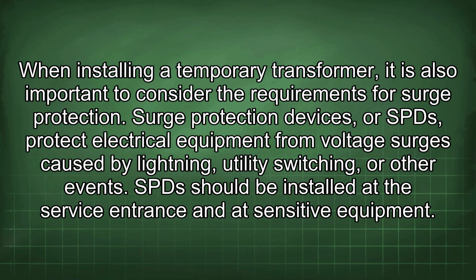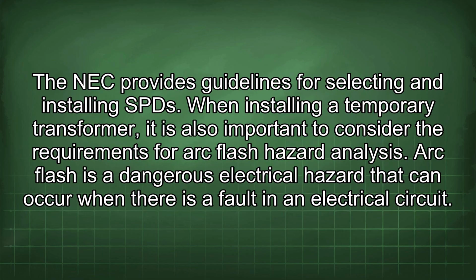When installing a temporary transformer, it is also important to consider the requirements for surge protection. Surge protection devices, or SPDs, protect electrical equipment from voltage surges caused by lightning, utility switching, or other events. SPDs should be installed at the service entrance and at sensitive equipment. The NEC provides guidelines for selecting and installing SPDs.